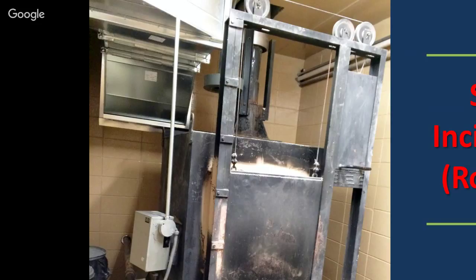So what happened was they had an HVAC upgrade for the building. They put rooftop air handling units, new VAV valves, a bunch of stuff, and they served the vivarium on that top floor. But what they didn't think about was this existing incinerator and the stack sticking up through the roof. After that project was done, they started getting indoor air quality complaints because the incinerator smoke was getting sucked back into the air intakes.